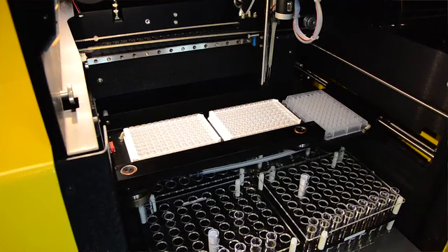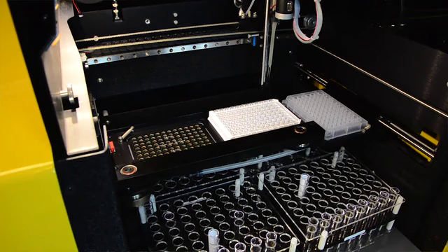Now, just as we're able to keep the footprint smaller with a small compact LED reader, we also do not need a chamber for an incubator. We do our incubating directly on top of our microtiter plate carrier, where you see the 2 microtiter plates. Now, as I take this off, you will see holes. Those holes are for the reader, so that the reader can read well by well. Now, the other things that you see on the plate are resistors. Now, they're on the microtiter plate carrier.